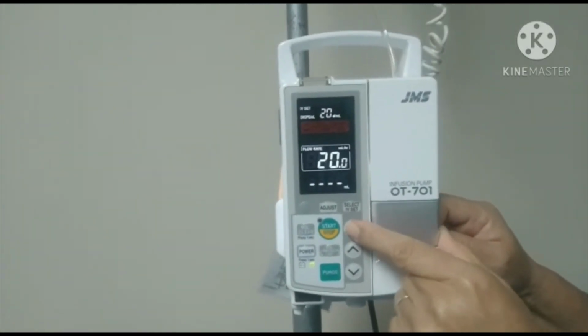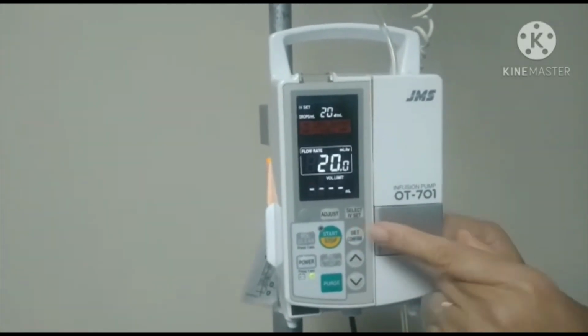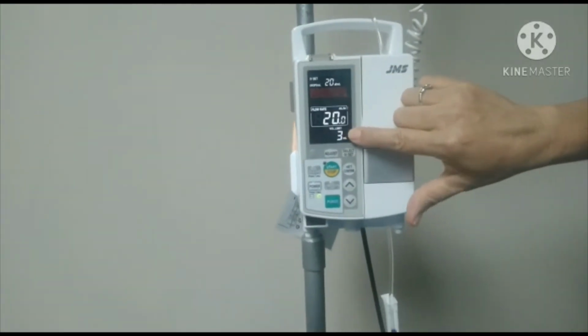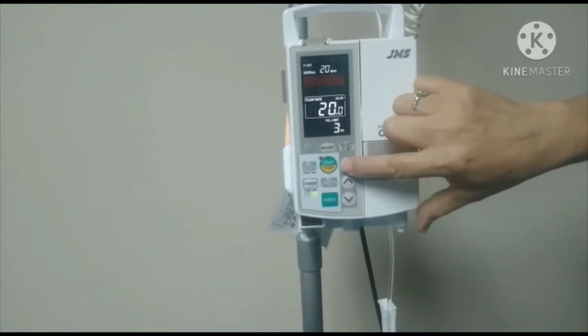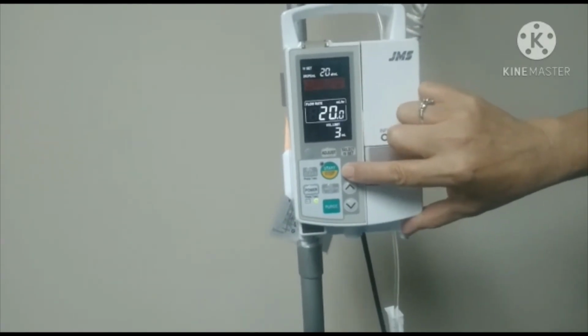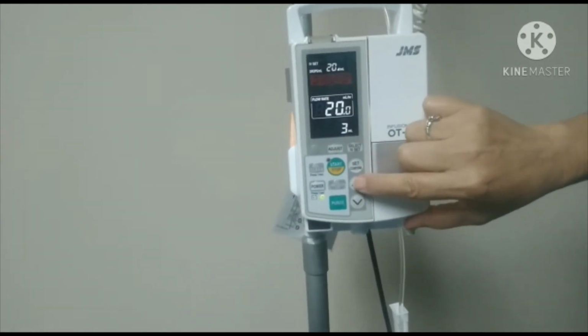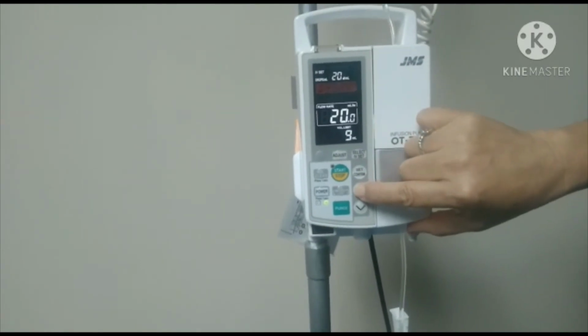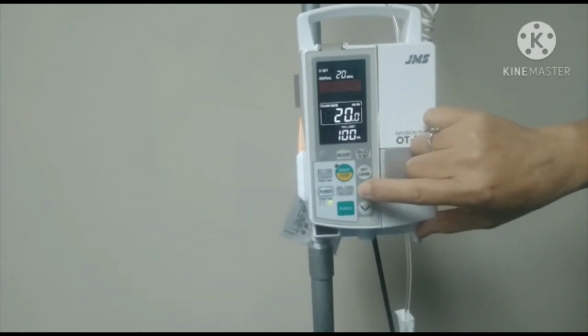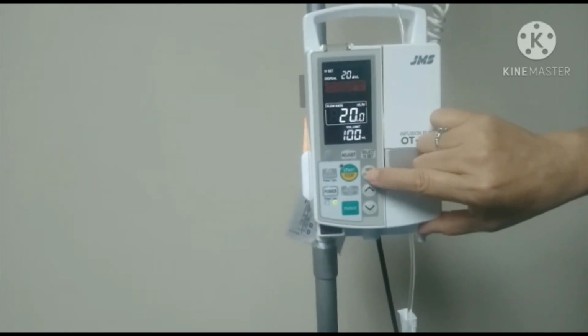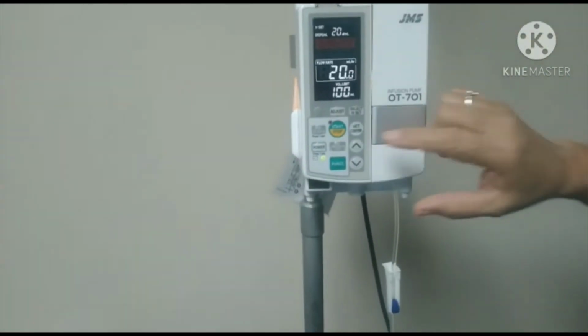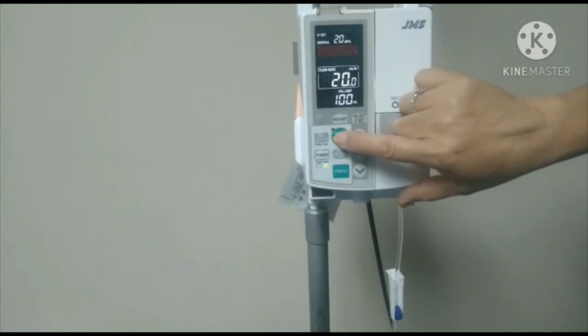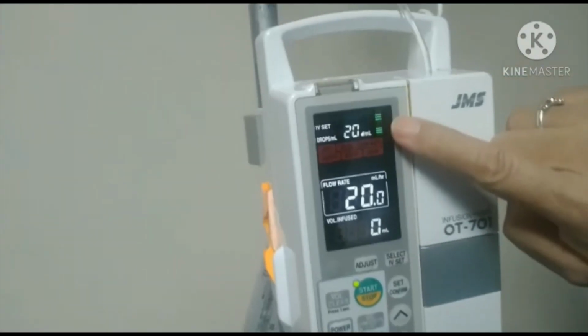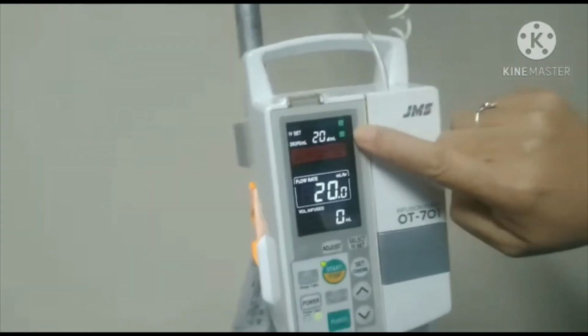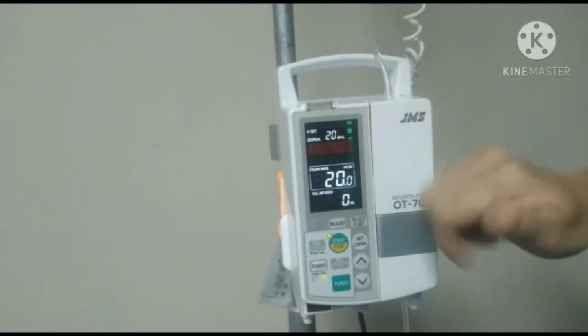The only thing left is to let the machine know how much fluid it has to monitor. This is important because the machine can end up pushing air into the patient's vein if it is not adjusted correctly. Press the Set button twice and enter the total volume of fluid that you have hung. Confirm by pressing the Set Confirm button. You press the Start button to have the machine function and see the fluid run. Now it's time to hook this up to the patient and monitor for infusion alarms to indicate things like air bubbles, fluid exhaustion, or occlusion.